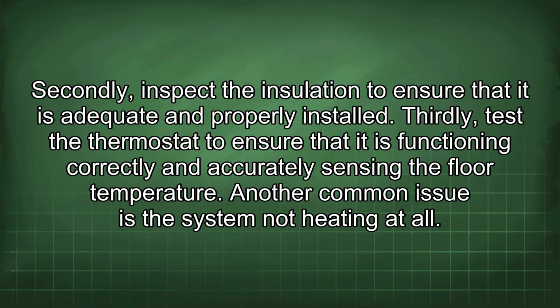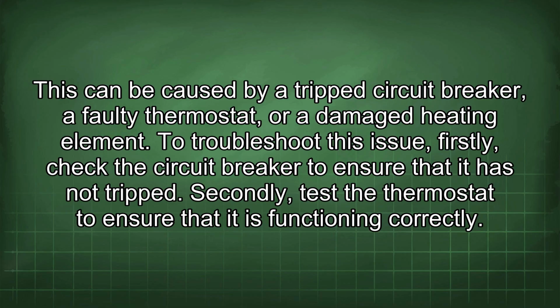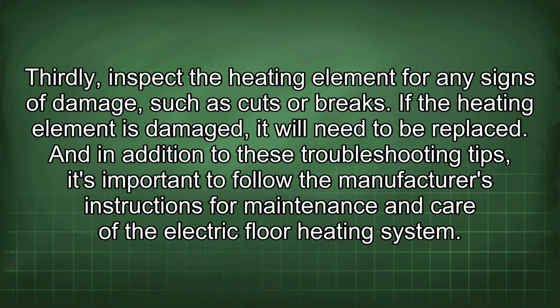Another common issue is the system not heating at all. This can be caused by a tripped circuit breaker, a faulty thermostat, or a damaged heating element. To troubleshoot this issue, firstly, check the circuit breaker to ensure that it is not tripped. Secondly, test the thermostat to ensure that it is functioning correctly. Thirdly, inspect the heating element for any signs of damage such as cuts or breaks. If the heating element is damaged, it will need to be replaced.